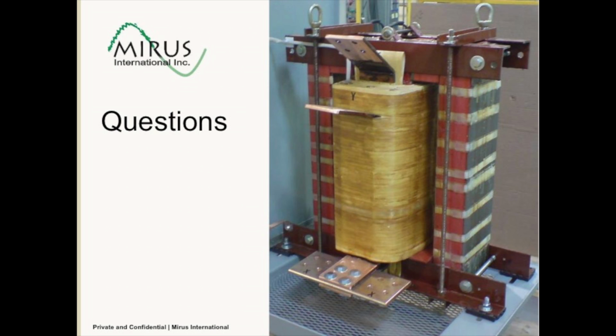So in order to limit that, we would need to put in impedance in the neutral. That can be done either with an NGR that inserts impedance, or with an NGI, neutral grounding inductor. So we would recommend the NGI. The NGI, because we're dealing with inductance rather than resistance, presents higher inductance at 3 times the frequency than it does at the fundamental frequency. So again, it'll block that return current without affecting the fault level as much. So those installations, you'd need it.